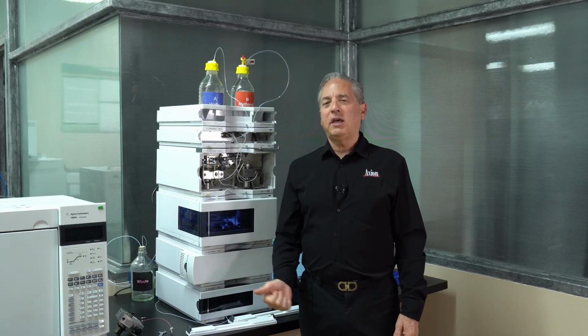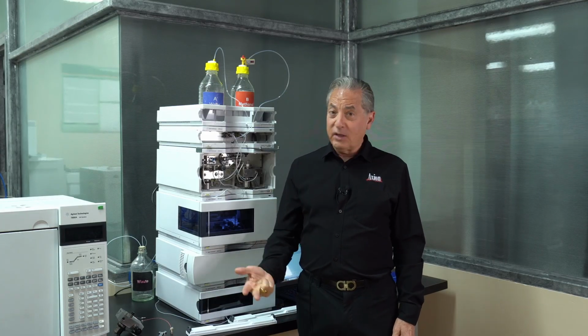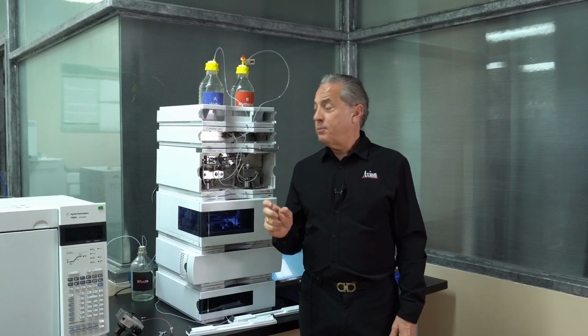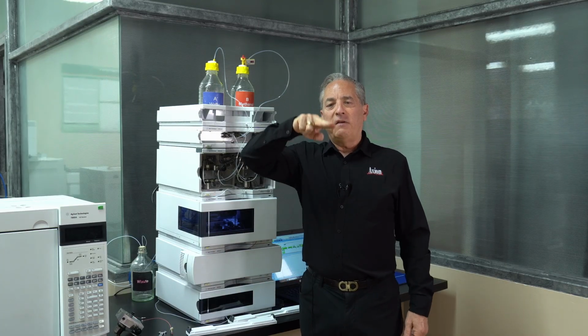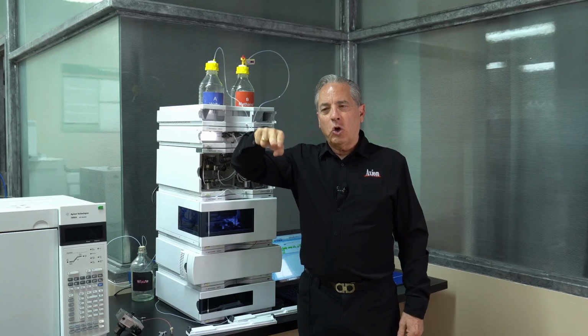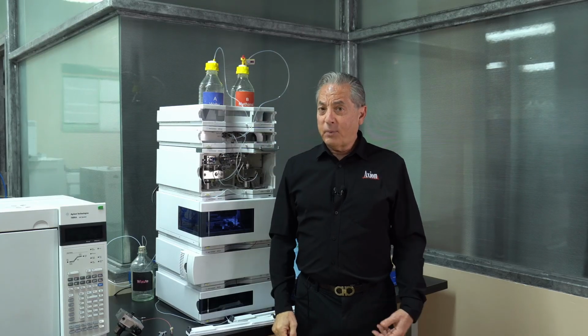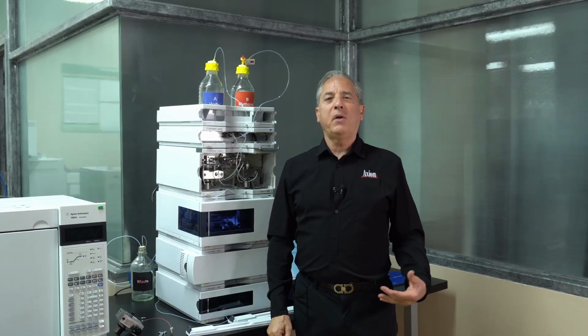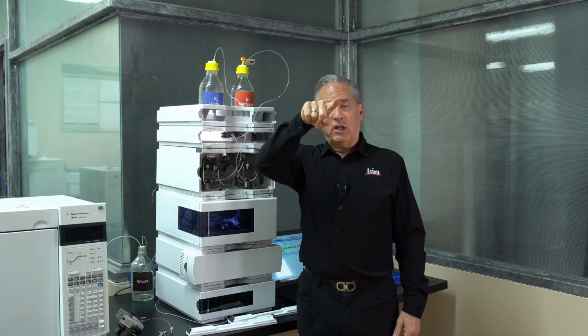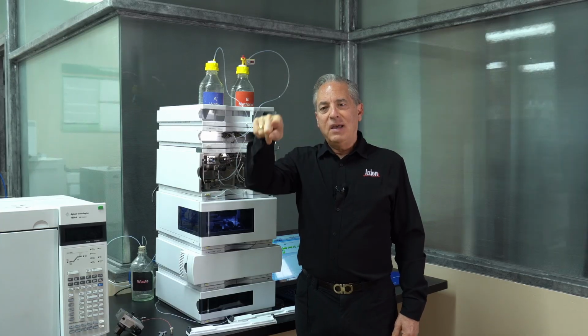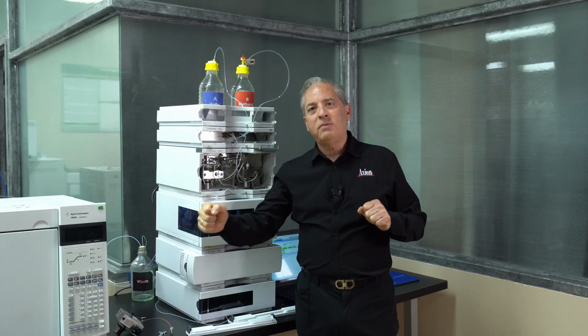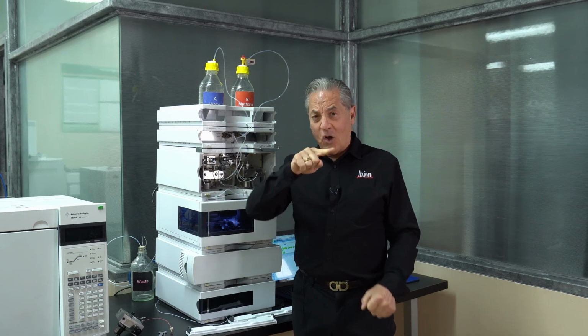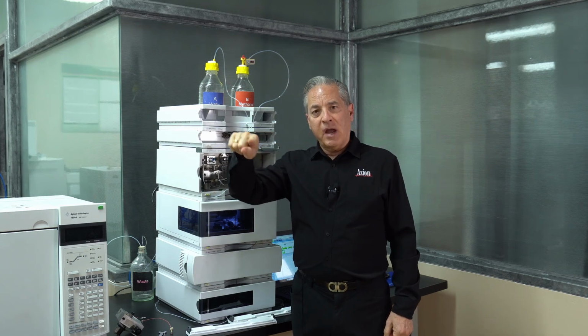If you have a leak, a check valve or a pump seal that's wearing out, or any little imperfection in the pump, you're going to see a variation in the pressure. The pressure ripple, if it's a pump problem, will be very periodic, very normal. In other words, it'll look like a sine wave. So this is pump noise. Notice the pump is doing the same thing, the same way, at the same speed all day long, so the noise is very periodic.